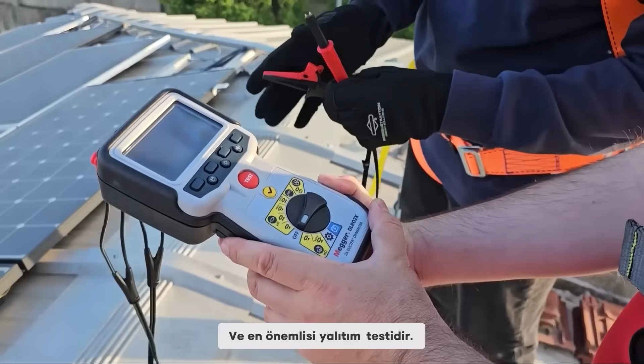Obviously, when you're testing insulation on a string of panels, you normally do it during the daylight, so there's active voltage. But with our type of instruments, you can still do the insulation test. A lot of people understand the insulation test. When I ask people who are doing installation what testing they have done, usually they just say this one. They default to this one, which is great, because any insulation weakness, whether in the panels or the cables or the connections, is a big problem.